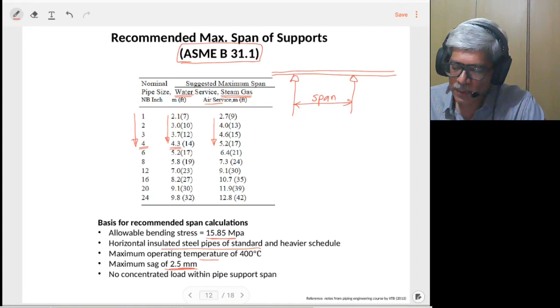Next, the other guidelines are as follows. The next guideline is to provide the support as close to the concentrated load as possible. So if your pipeline is having heavy loads such as a valve, typically valves are bulky and they are having more load. So provide a support near to the heavier part. If it is near to the load, the bending moment effect will be smallest. So that is the idea. If you have heavy valves or heavy flanges, you provide the support as near to them as possible.